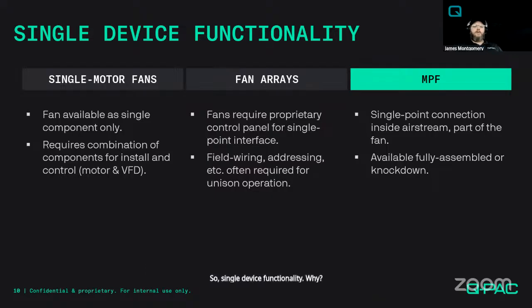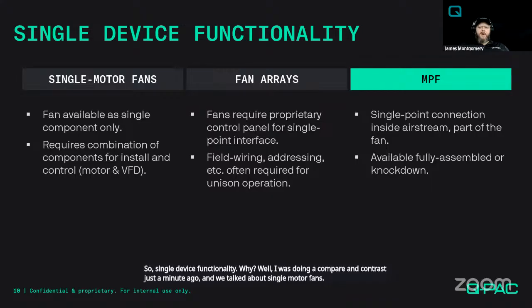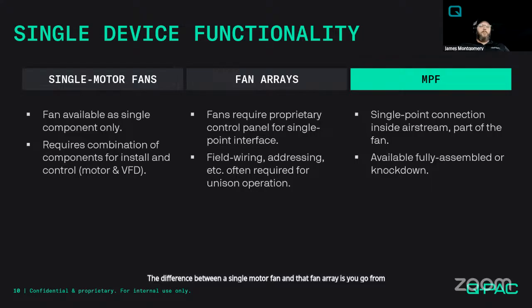Why? Well, I was doing a compare and contrast just a minute ago, and we talked about single motor fans. I said fan arrays, and then now the MPF. The reason why we're pulling MPF off to the side and not considering it as an array anymore is because at Q-PAC, we built arrays. We did it for a long time. We were a Daikin modifier. And I like to think that we built some of the best arrays that are out there. The difference between a single motor fan and that fan array is you go from one item to multiple, and sometimes that includes complexity. And so what we've done is re-engineer and re-architect the way we built this system to where you get the simplicity of a single motor fan with all the benefits of a fan array.